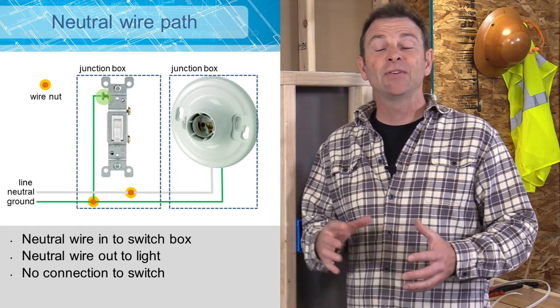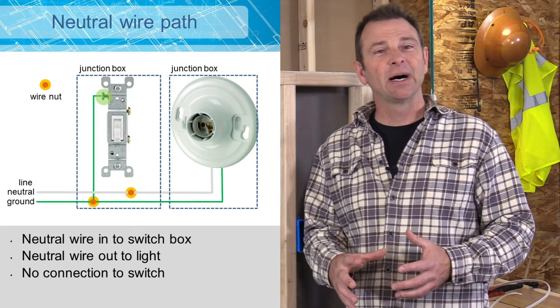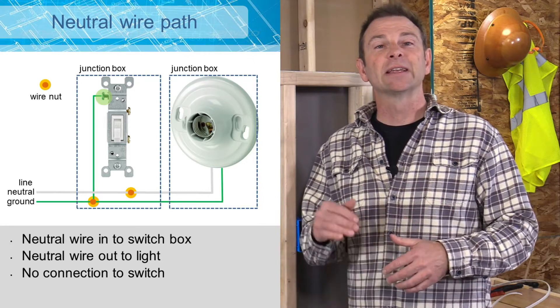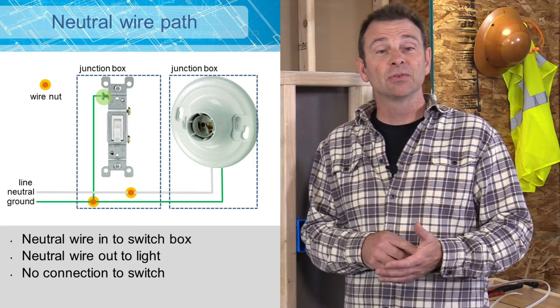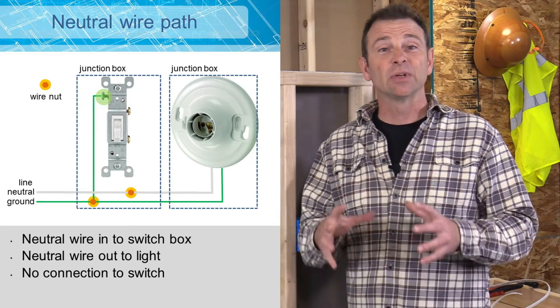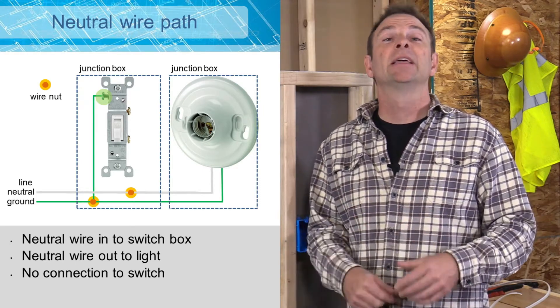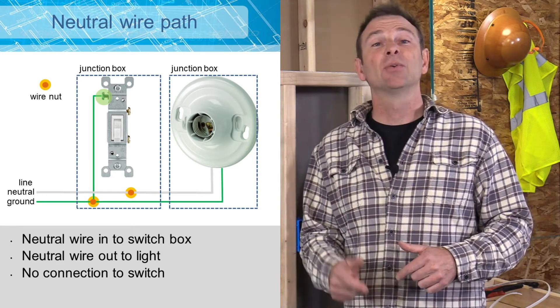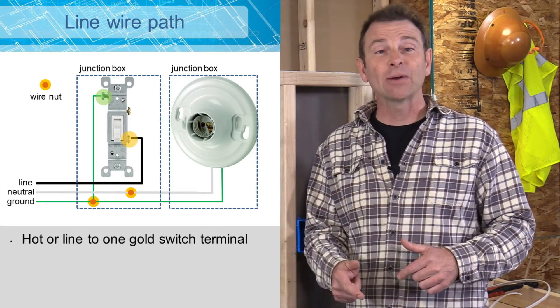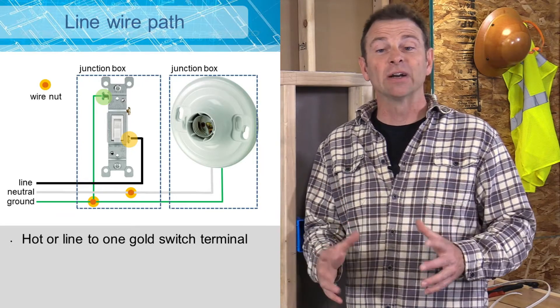Next up is our neutral. If you notice, there's a connection in the box with the neutral that then leaves the box. There's no physical connection of the neutral wire to our device, which is our switch at all. The only wires or conductors that are going to connect to our switch are going to be our black wires, which are our hot wires.